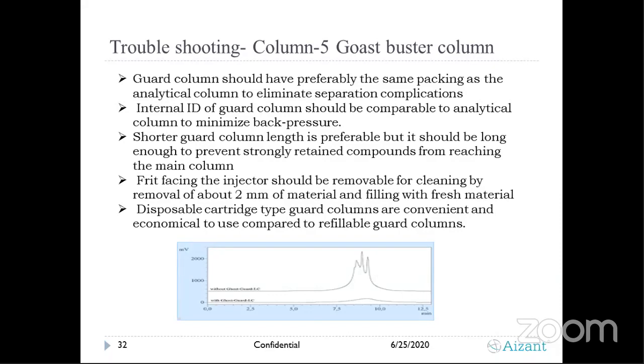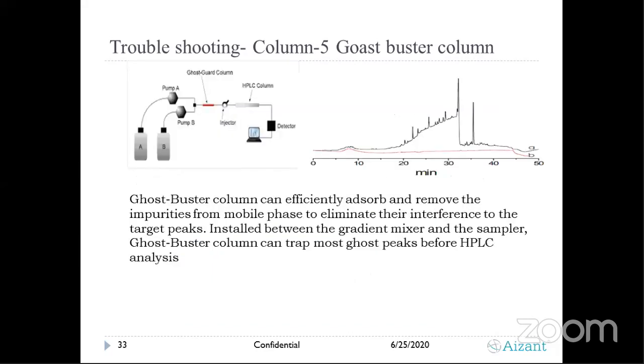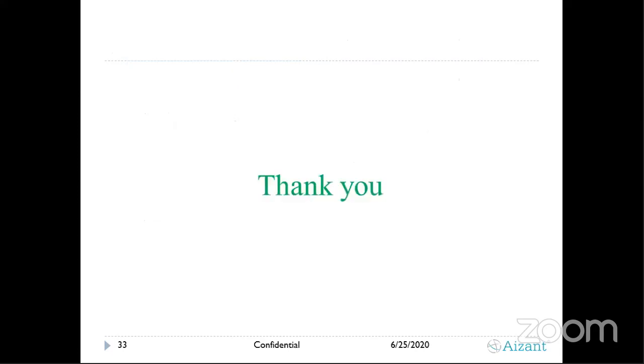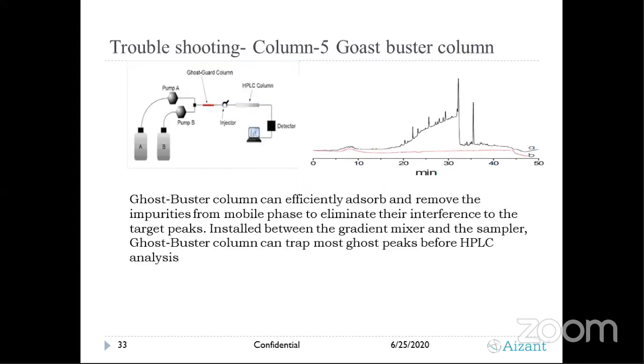It's particularly used for mobile phase contaminations to be removed through a ghost peak arrestor. Now in this slide you can see where it has been attached. Guard columns are attached to the HPLC column, but the Ghostbuster column is attached before the injection. So whatever contaminations come from the mobile phase are taken care of by the Ghostbuster column, and a neat and clean mobile phase is given to your HPLC column.